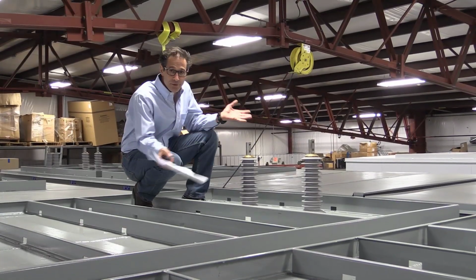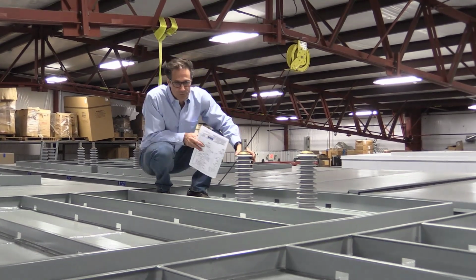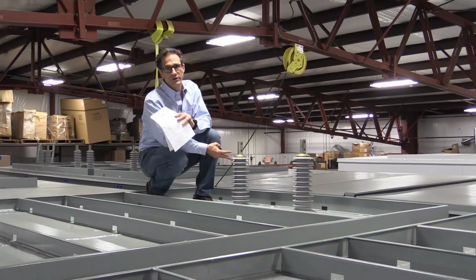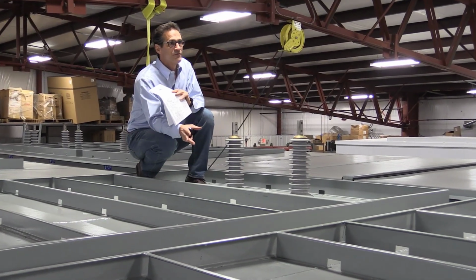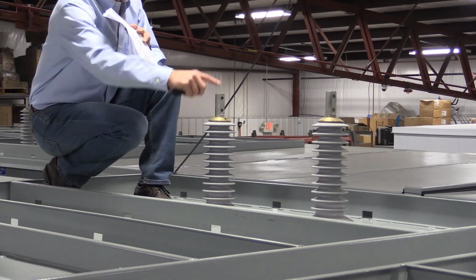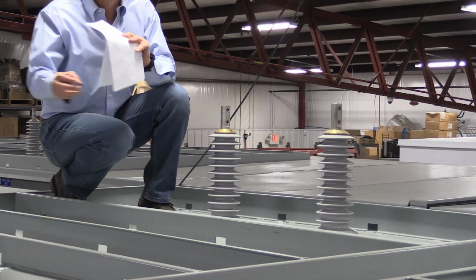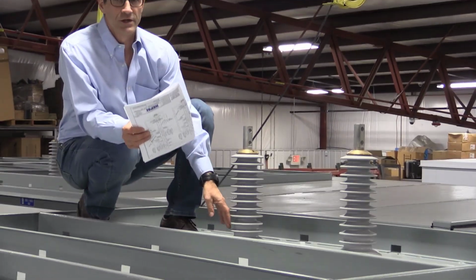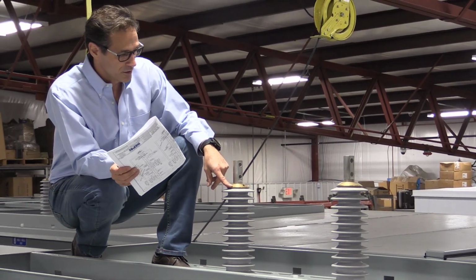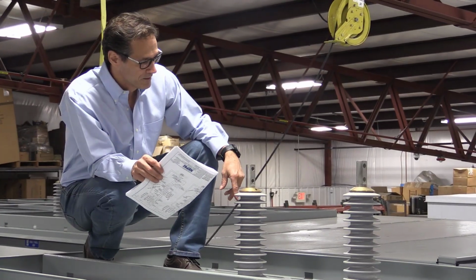All right, so I'm on top of the equipment after that long climb. What I want to first point out here is we have bushings protruding through the ceiling. And if you recall from the first part of the presentation, there are the resistors on top here. This represents one phase, and this is stage 1, phase A resistors. These are the bushings that come through the roof that connect across the aux capacitor and the reactor in the C high pass filter branch.